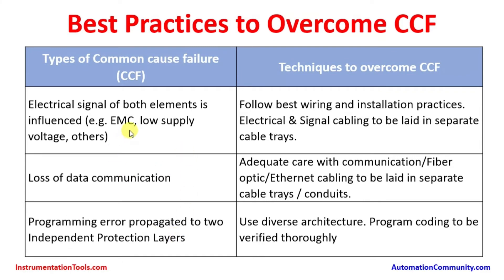Electrical signals of both elements can be influenced if two transmitters share wiring. There may be electromagnetic interference or low supply voltage. To overcome this, follow best wiring installation practices: electrical and signal cabling should be laid in separate cable trays.